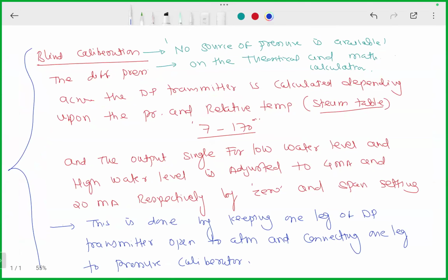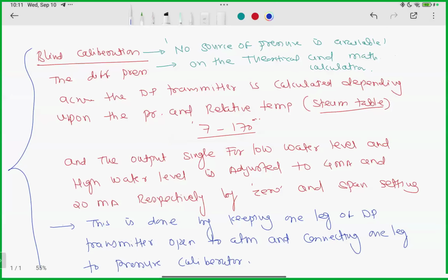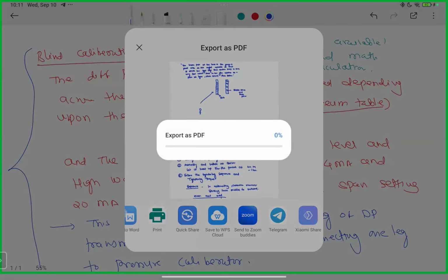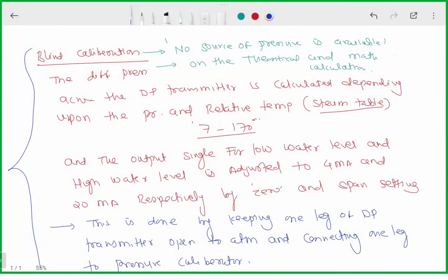For example, if you are measuring pressure and you want to measure between 10 bar and 20 bar, corresponding to 10 bar what should be your signal? 4 milliamp. That means you can read your lowest possible pressure with 4 milliamp. But what is your range?